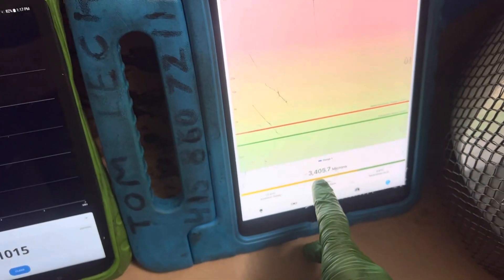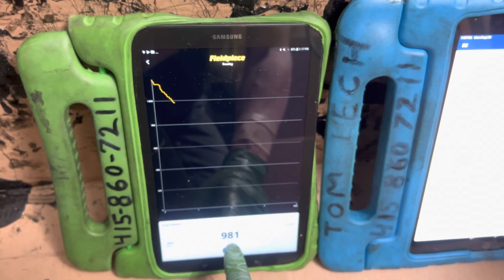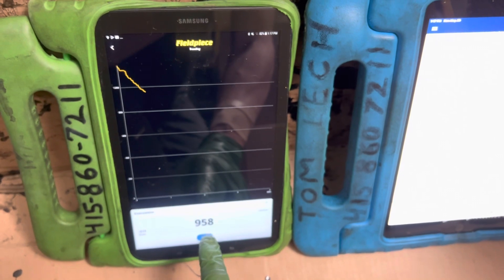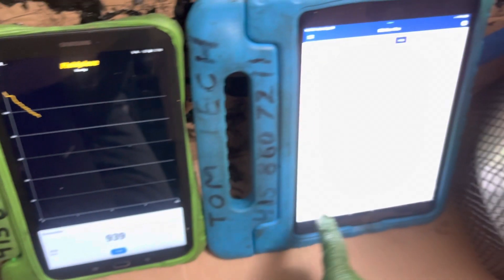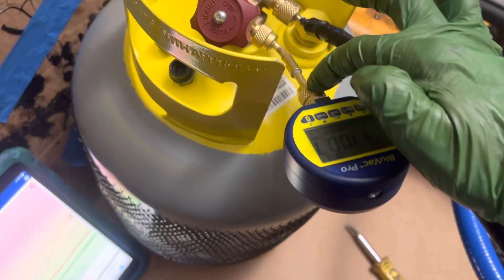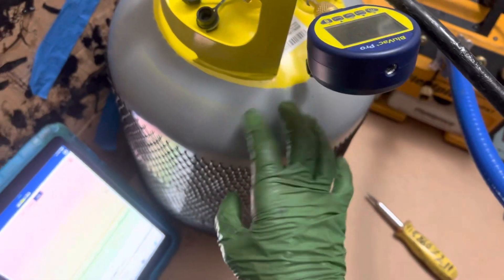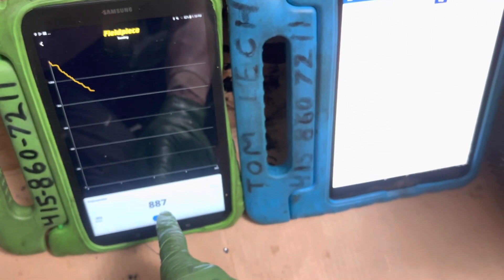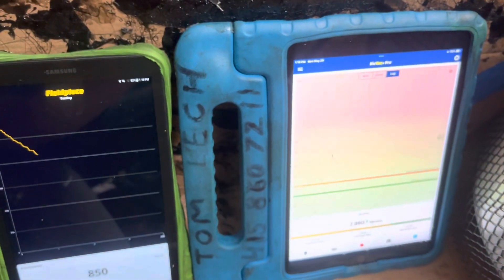Okay, it's showing our reading right here is this reading right here. This is in the gauge. This is in the tank. Do you see the difference? This is why you do not use refrigerant gauges, especially while it's under vacuum, to determine what your vacuum is in your system. Because this is the system where this is connected, it goes down to a tube that goes into the tank, reading the true vacuum inside the system. This is reading the vacuum inside the gauges—it's a huge difference.